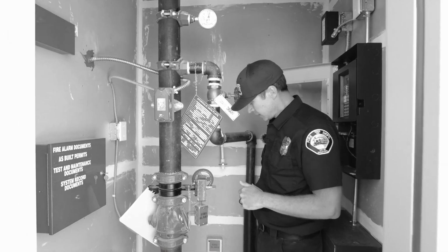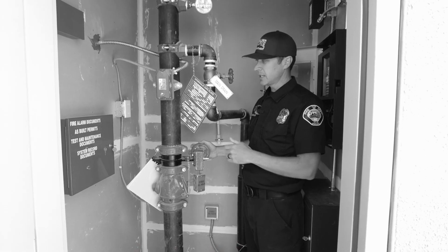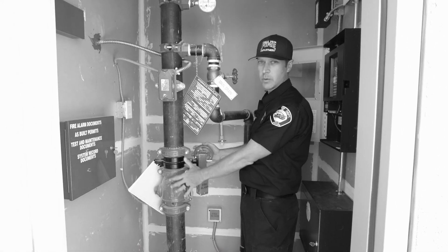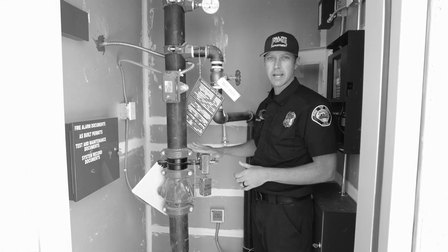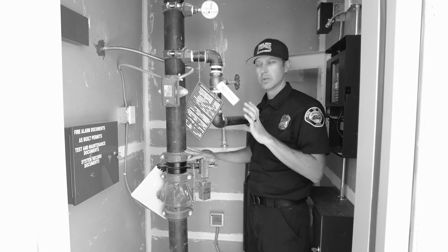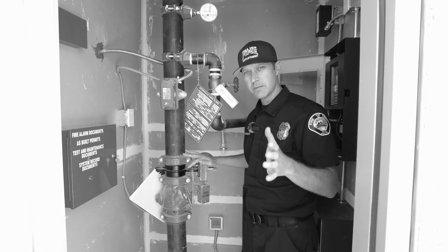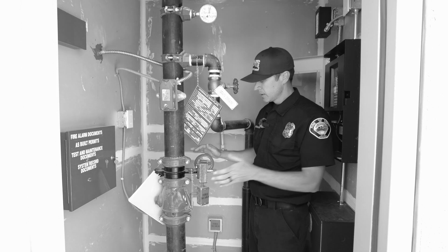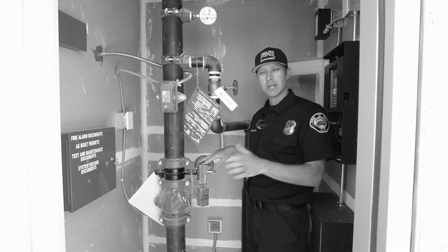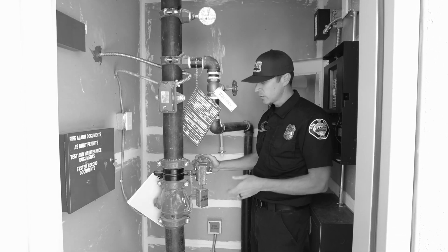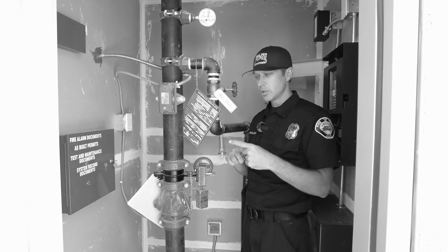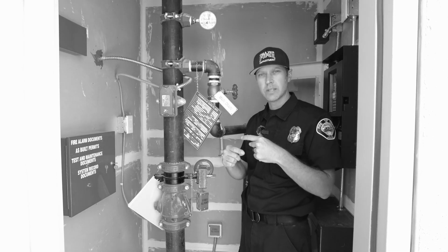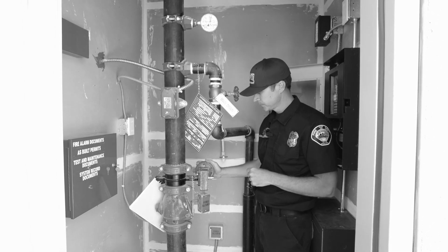If the main drain doesn't stop after a couple minutes and you feel like you still have water flowing through the system, we haven't actually shut off the system. So in a scenario where you have a PIV or a backflow preventer, you may think you shut the right system off, but you didn't, and the water is still flowing. You'll want to go back through that process and ensure that you found the right control valve.